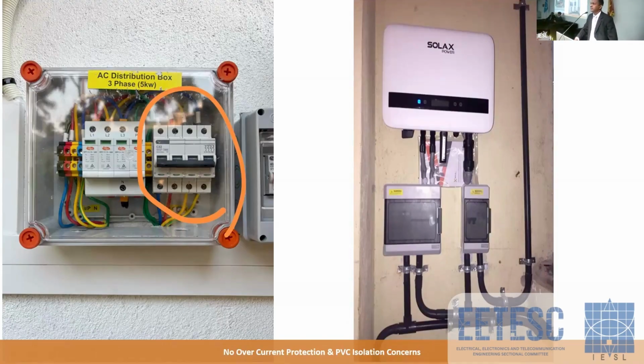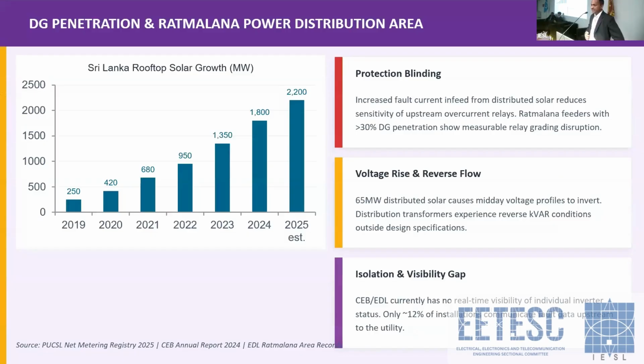PUCSL and CEB imposed. This is how our engineer Amila explained the growth of renewable energy: within 2.5 or 3 years, 2,200 megawatts of rooftop solar installations were added to the national grid. Because of these installations, as far as safety is concerned, we could see protection blinding, bidirectional flows of current. Some protective devices can't measure actual fault currents because of those bidirectional current flows.